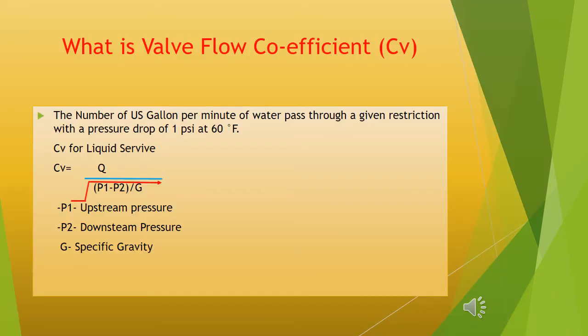What is valve flow coefficient? CV is the number of US gallons per minute of water passed through a given restriction with a pressure drop of 1 pound per square inch at 60 degrees Fahrenheit. Valve coefficient is directly proportional to flow and inversely proportional to the square root of delta pressure.